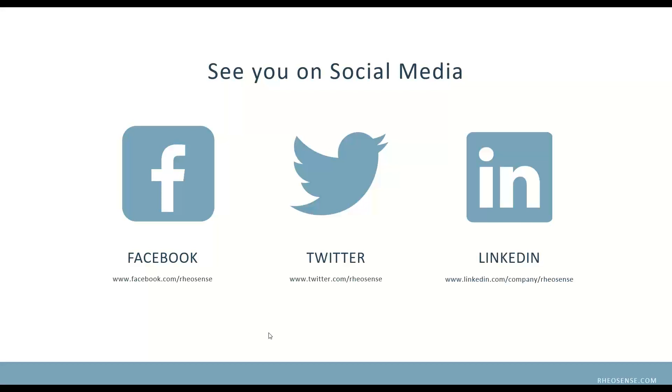Good morning, everyone, and welcome to our VROC Initium 1 Plus Automated Viscometer Demonstration Webinar. This webinar will be hosted by our in-house rheology expert, Dr. Stacey Elliott, along with our field service engineers, Nathaniel Graetz and Damian Villapadua. The VROC Initium 1 Plus is the leading automatic viscometer measuring viscosity with the highest accuracy and repeatability. Equipped with automatic sample loading and cleaning, it measures absolute viscosity as a function of shear rate across a wide temperature range, allowing for unique viscosity fingerprinting at our highest throughput, measuring up to four samples per hour.